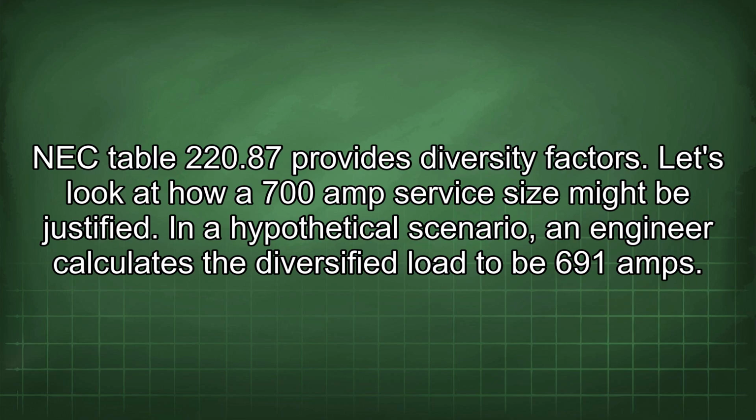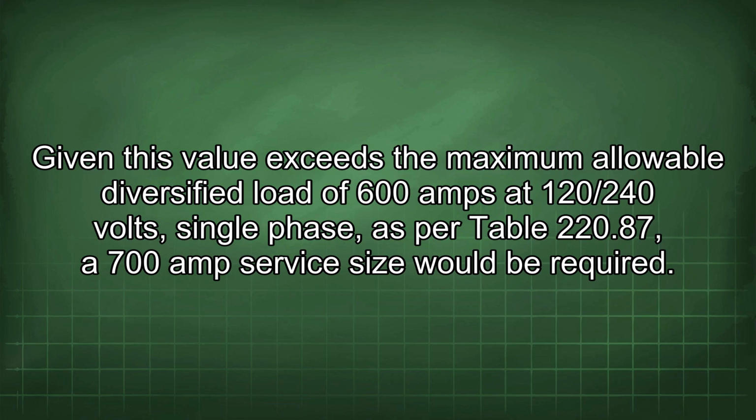In a hypothetical scenario, an engineer calculates the diversified load to be 691 amps. Given this value exceeds the maximum allowable diversified load of 600 amps at 120/240 volts, single phase, as per Table 220.87, a 700 amp service size would be required.